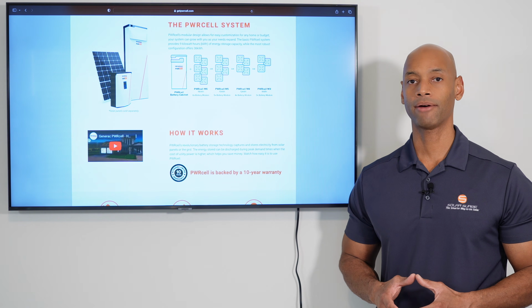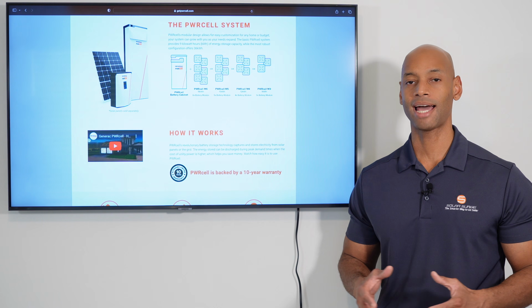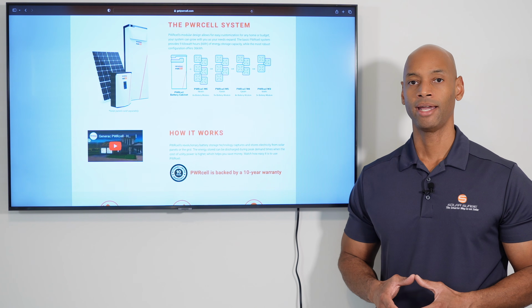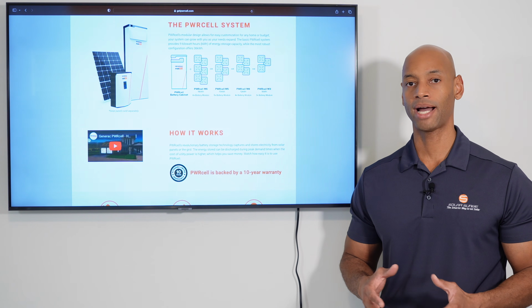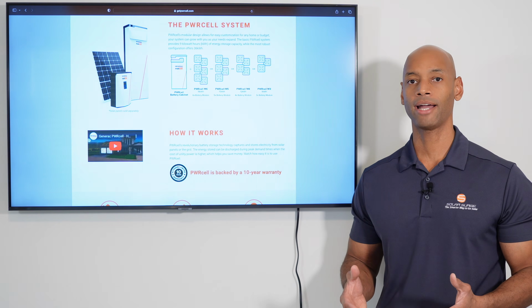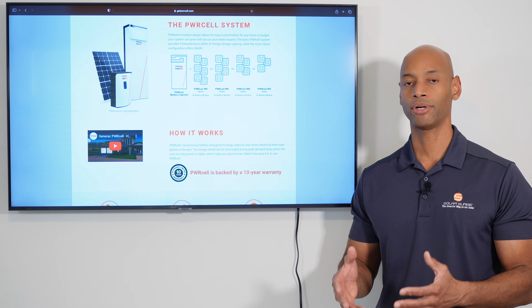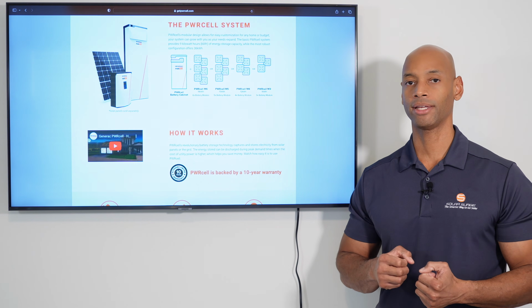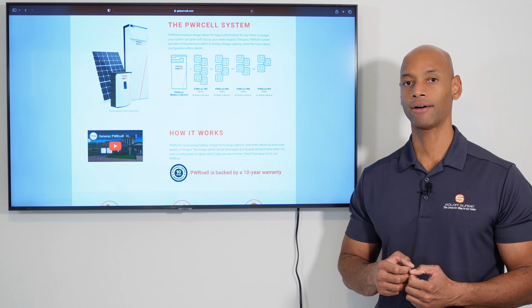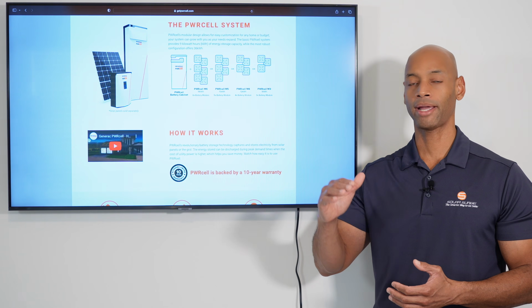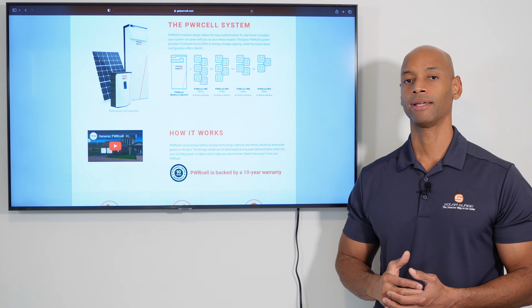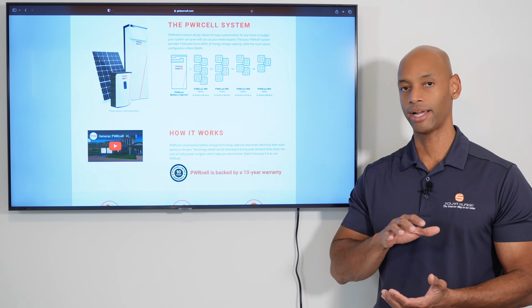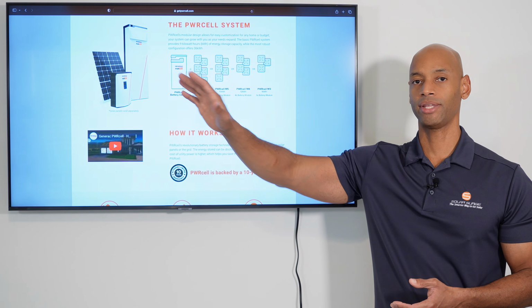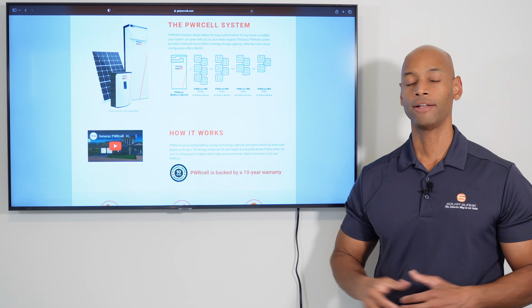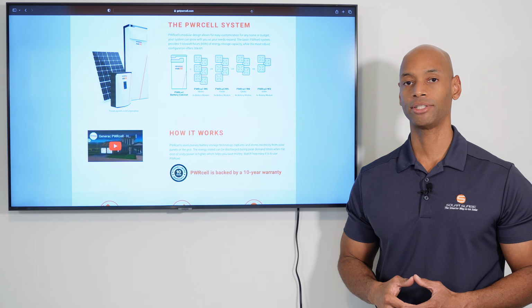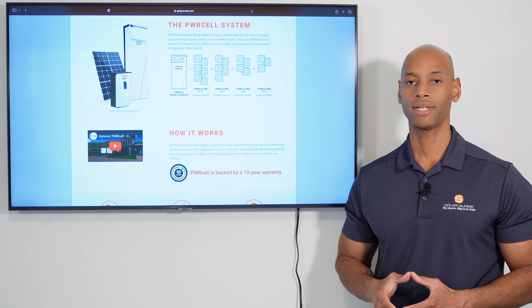Part of the Generac PWRCell system is a component called the Snap RS, or Rapid Shutdown. This component is actually required by electrical code so that if there's a fire in the house and firefighters pull out the electric meter and shut down the electrical connection to the grid, the solar panels are required to do a rapid shutdown. They need to disconnect power and de-energize all the way up to within 10 feet of the solar panels. In order to achieve compliance with the rapid shutdown requirement, Generac used a Snap RS device.